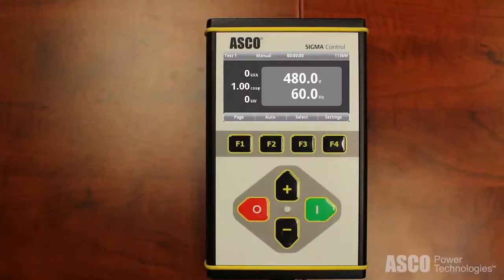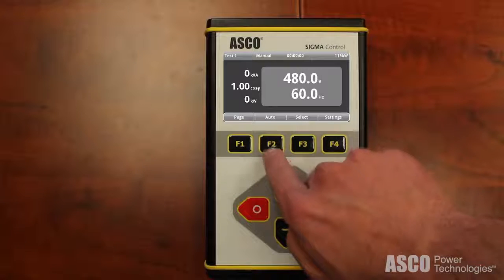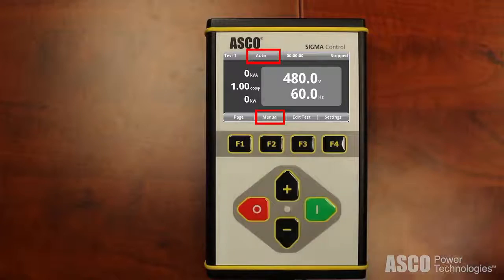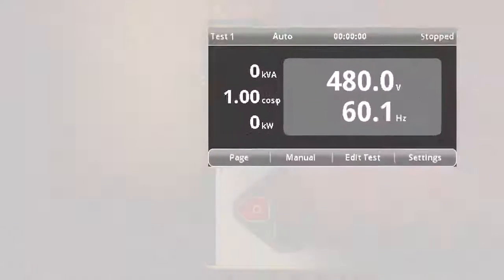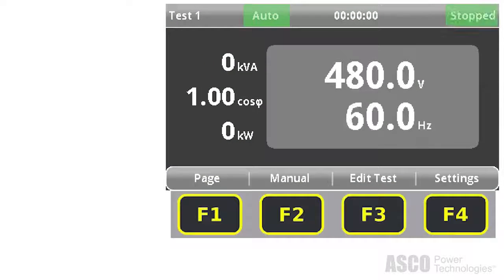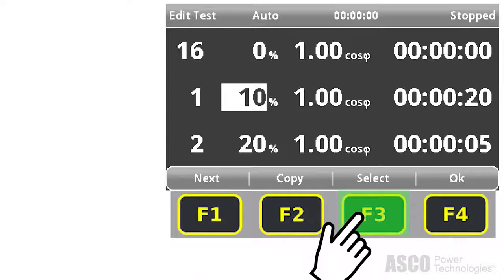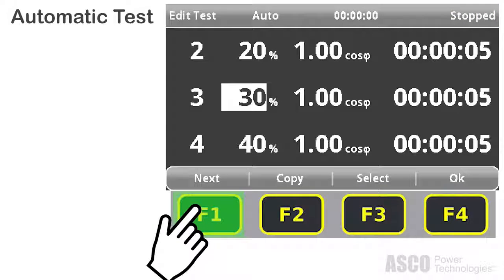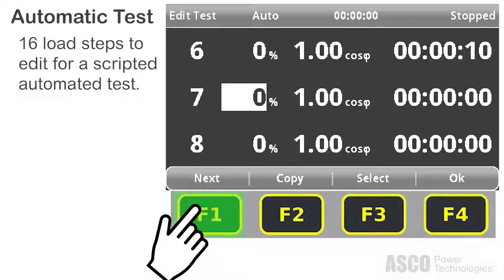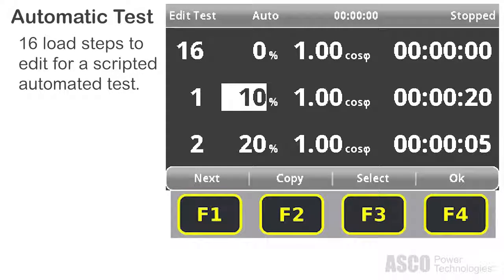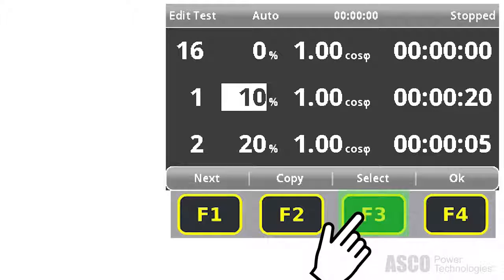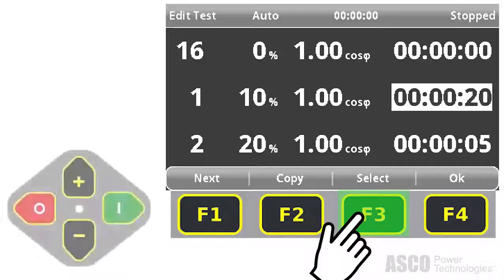The next way to do a test is with an auto test. So down here we're going to hit the function 2 button and click auto. You'll notice up top it says auto now and we are stopped. So then you hit the function 3 button to edit test. So you'll see there are 16 potential steps that we can go through and add or subtract. So with that we can do a percentage, a power factor, and a time duration.